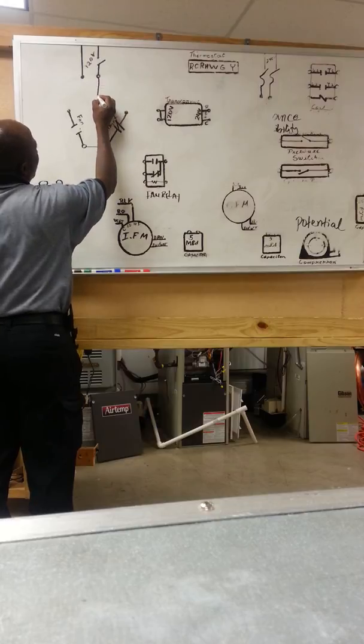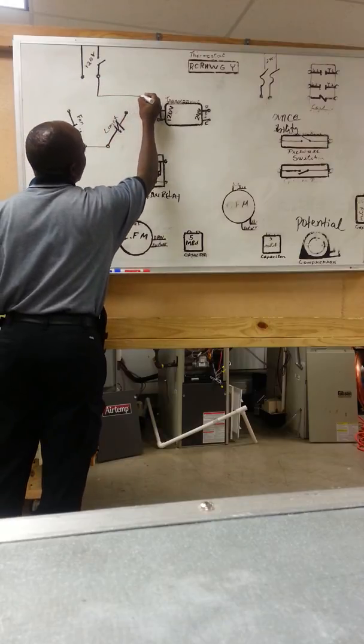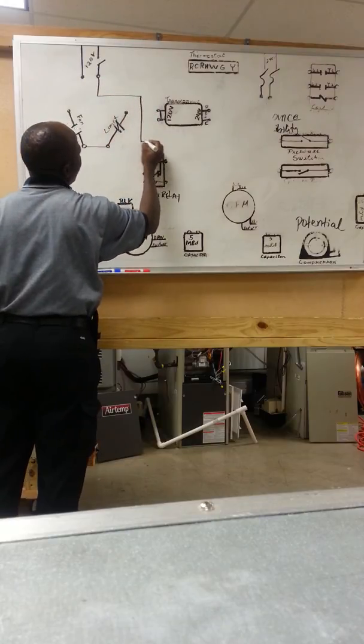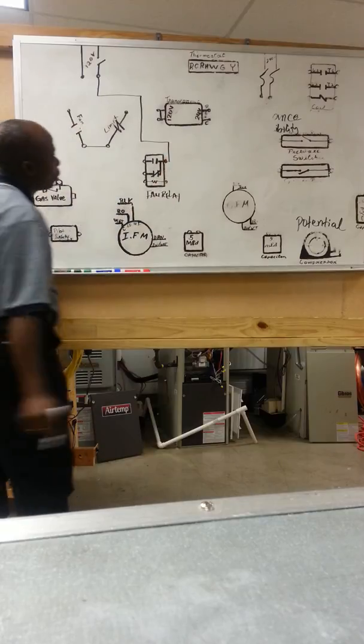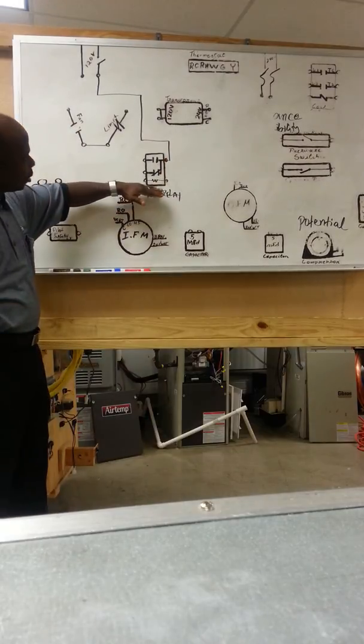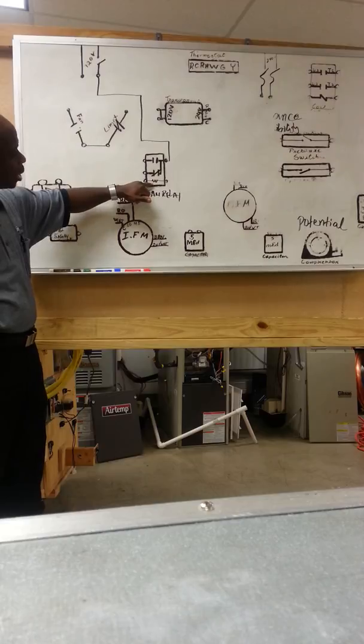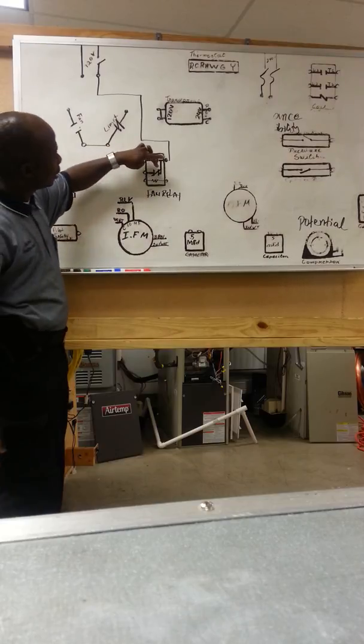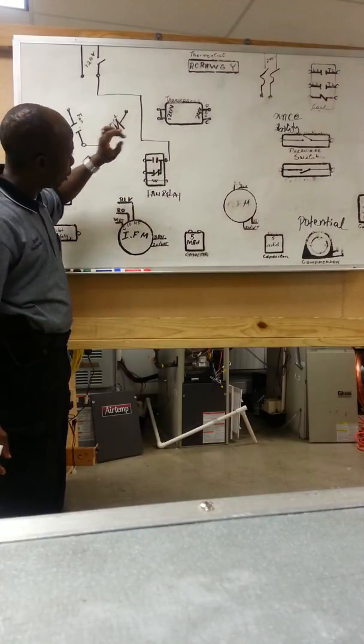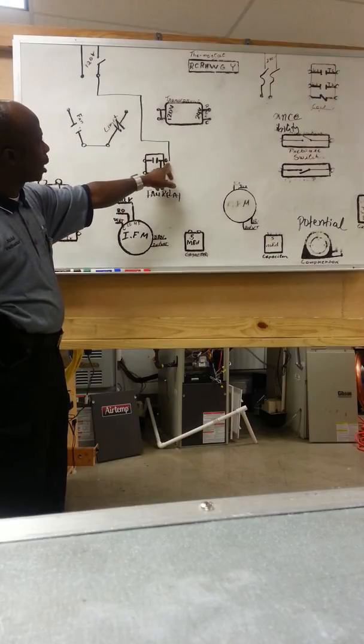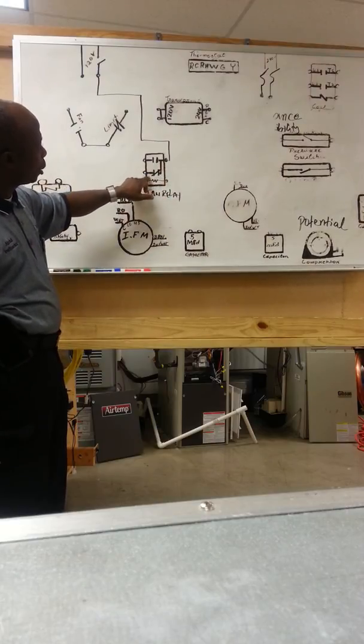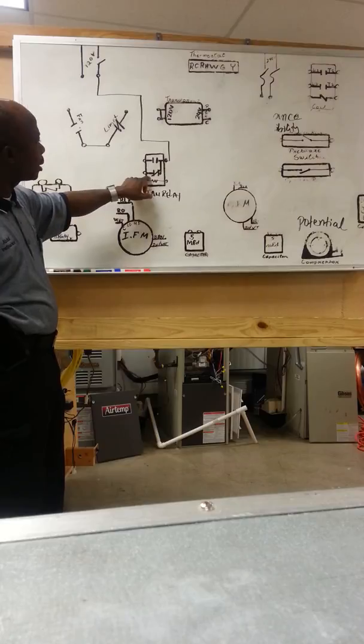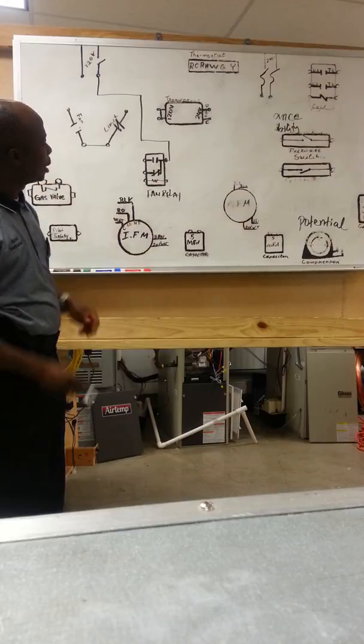It's going to come down, we're going to split. Come down and feed power to the common side of the fan relay. This fan relay down here is 24 volts. That's the coil side, that we call the load. And this is a normally closed, normally open. So once I send power to the common, there's power running all the way straight to the normally closed contact, and the normally open stays open.